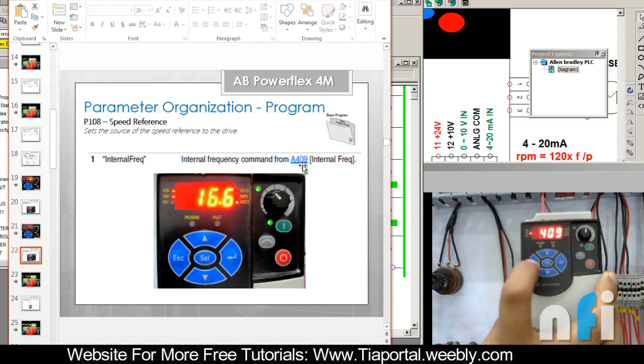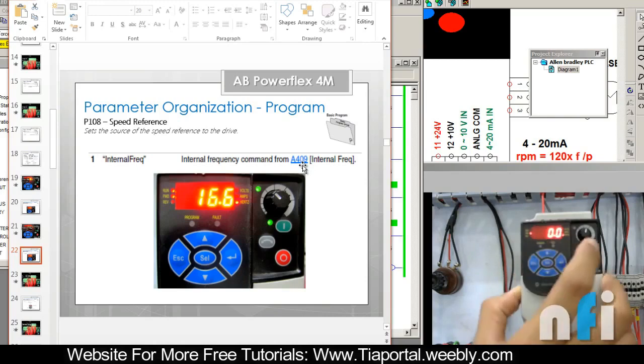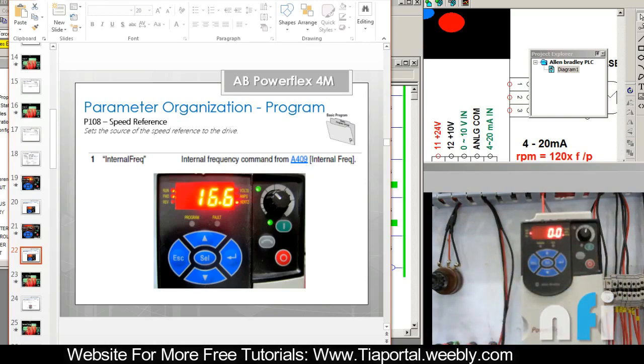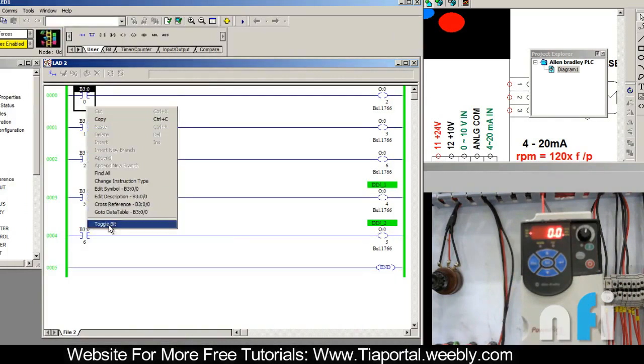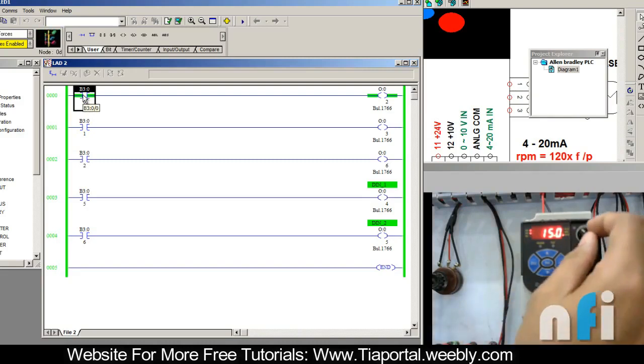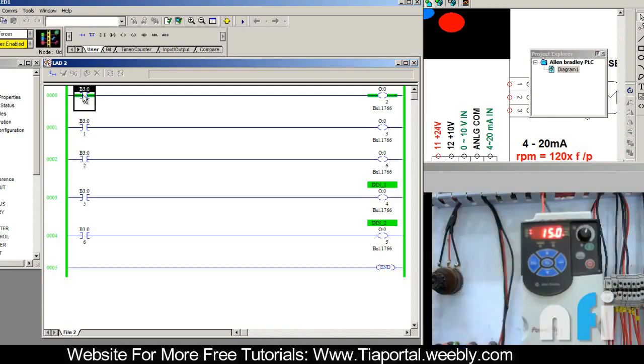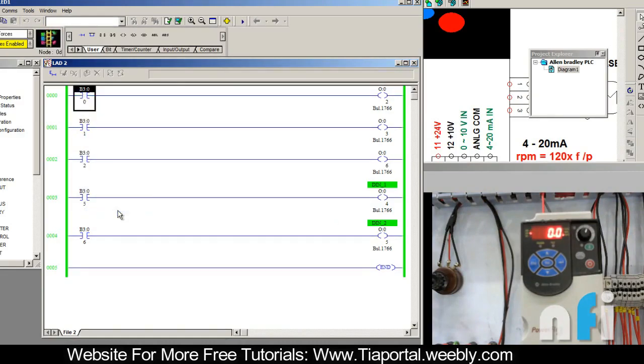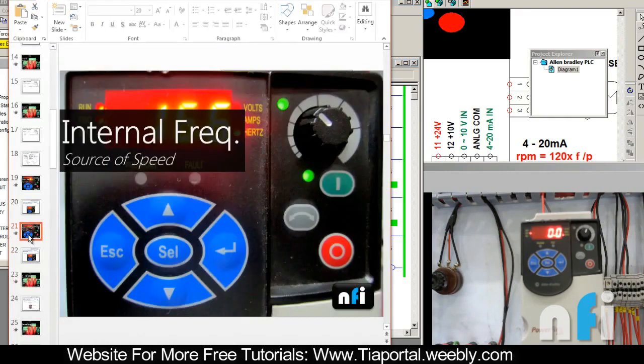Now when I go back outside and initiate this drive from the PLC, it will move to 15 Hz by itself. The frequency will not be controlled by the potentiometer because that light is not on — this is internal frequency. So whenever you run the drive, it will go to 15 only. That's the set frequency, and you can change this frequency as needed.